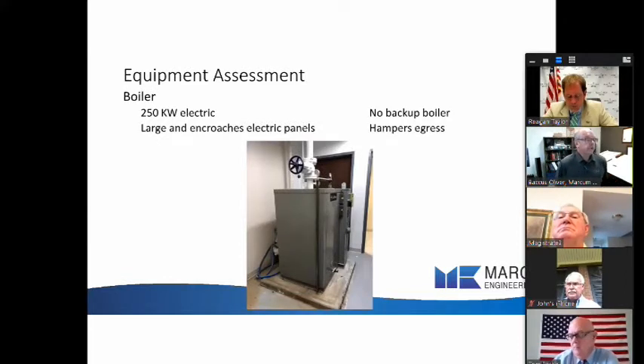The next equipment was the boiler. This is on the lowest level. It's all electric, so this is a 250 kW boiler. It's kind of surprising that a building of this size uses electricity only. There is no backup boiler. You only have one of these. This boiler is very large and is in the electrical room, and it encroaches the space required for electrical panels to meet NEC, and it hampers egress. If you'll notice, just beyond it, above the boiler, is the second exit for the room that's required by code, but you can't get to that door.